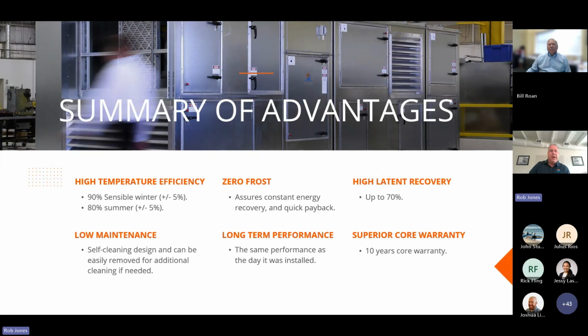So in summary, high temperature efficiency. We're 90% sensible in the winter and 80% in the summer. Zero frost. This is the big takeaway, is we don't require a preheat or defrost strategy in normal conditions. And normal conditions to us is -40 with a 25% relative humidity. This is our jobs that we have in Northern Canada and the Arctic.